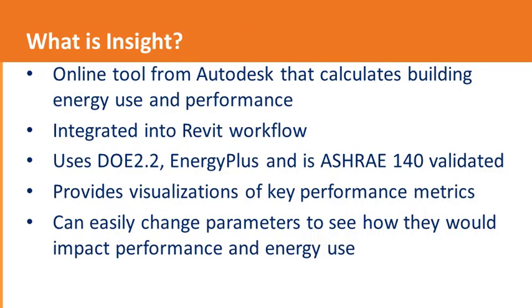What is Insight? It's an online tool from Autodesk that calculates building energy use and performance. It's integrated into Revit, has no additional cost, uses Energy Plus, DOE 2.2, and is ASHRAE 140 validated. It provides visualizations of key performance metrics, and we can easily change parameters to see how they would impact performance and energy use.